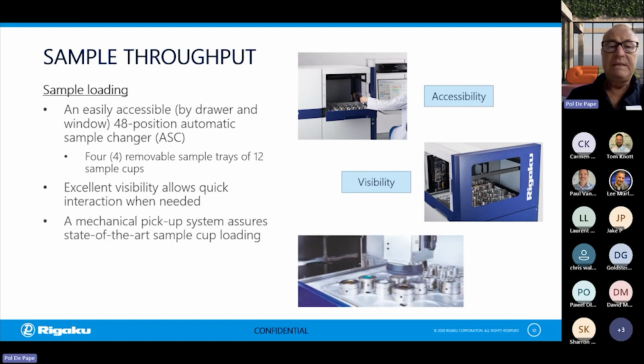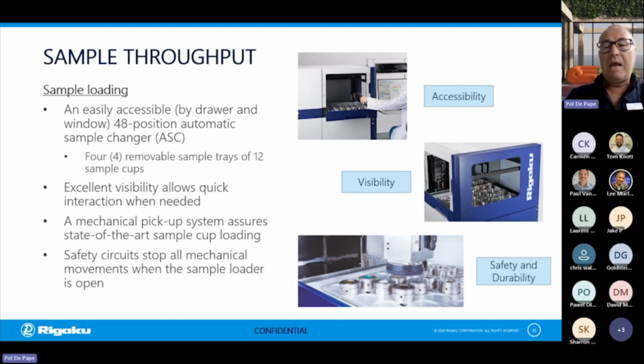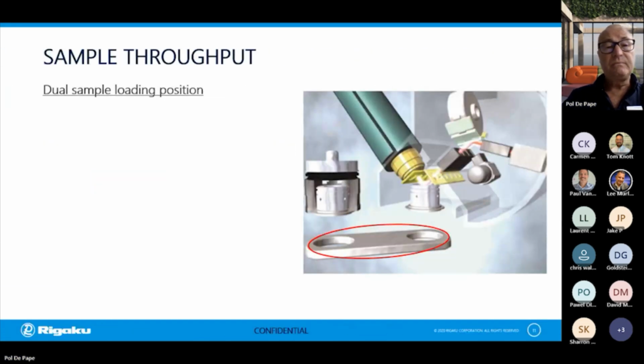One never knows, of course. We are using a mechanical pickup system, and this assures really state-of-the-art sample cup loading. So no pressed air, the mechanical way is the best way to grab the sample cups. And we have, of course, built in the necessary mechanical safety circuits to stop any mechanical movement if something would go wrong within the sample loader. Important to know is that we have a dual sample loading position. This means we have two positions, and as one sample is being analyzed, the other sample is already being loaded.